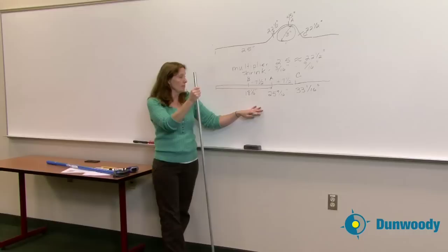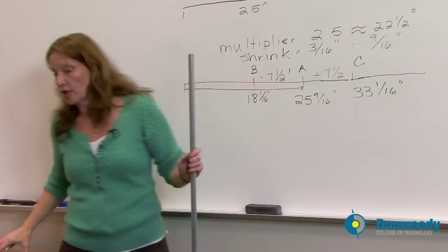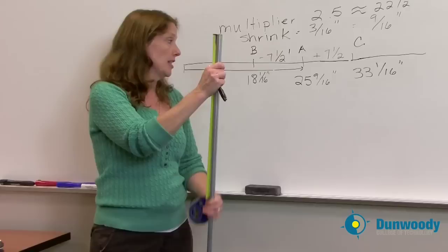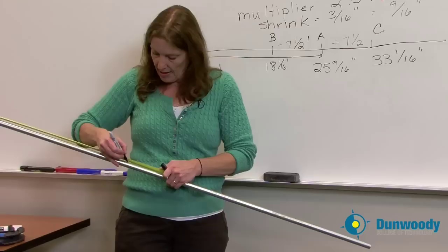Once again we'll use our problem from the board where we had a 25 and 9 sixteenths obstruction. I'm going to take my tape measure and come to the end of my conduit. I know that I want to start with my A mark, so I'm going to measure out that 25 and 9 sixteenths, remembering I did add 9 sixteenths for my shrink onto the value. I'm going to mark it at 25 and 9 sixteenths.